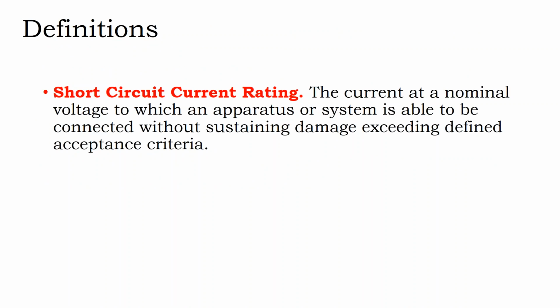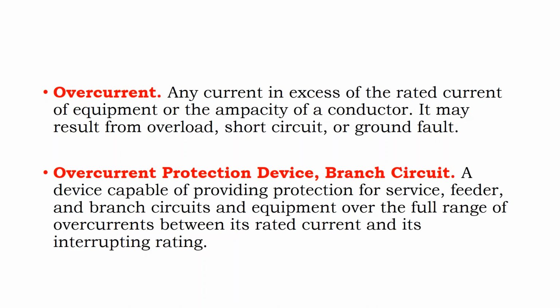We've got short circuit current rating: the current at a nominal voltage to which an apparatus or system is able to be connected without sustaining damage. So that's during a short circuit current, if the cables or equipment could be sized to short out but still work. Overcurrent would be less than a short circuit current. Your short circuit current could be 100 amps, but you're putting it on a 20 amp breaker because it's not supposed to have 100 amps. It's supposed to be at 15 amps.